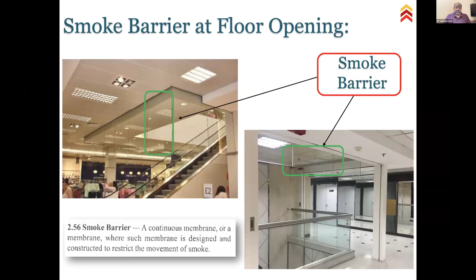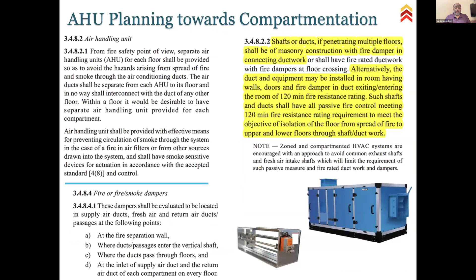As you read, NFPA 92 talks about barriers and pressure differentials - it does not talk about ACPH. The National Building Code of India also emphasizes compartmentation, which we started our talk with. If you compartment the building correctly with the right air conditioning system compartmentalized, the spread of fire is hugely controlled. This is a typical diagram most mechanical engineers would know for smoke mitigation measures.